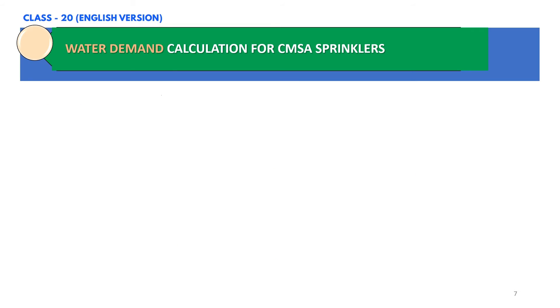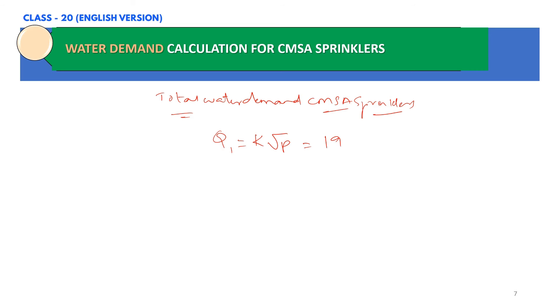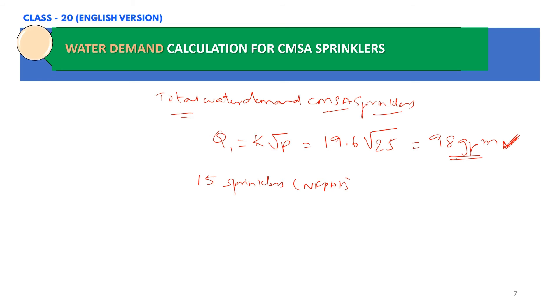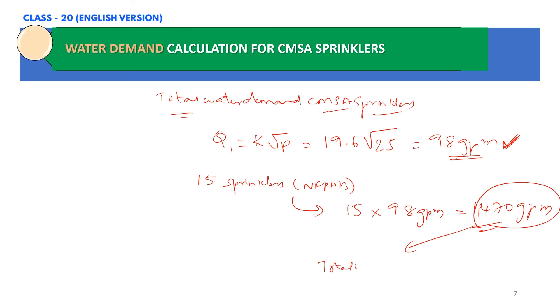In this slide, we are going to calculate the total water demand considering CMSA sprinklers. First, we calculate the demand from one sprinkler using the formula Q = K√P. K is 19.6 and P is 25 PSI, giving a flow of 98 GPM from one sprinkler. Since we are considering 15 sprinklers as per the NFPA 13 table, we multiply 15 by 98 GPM. The total sprinkler water demand is approximately 1,470 GPM.